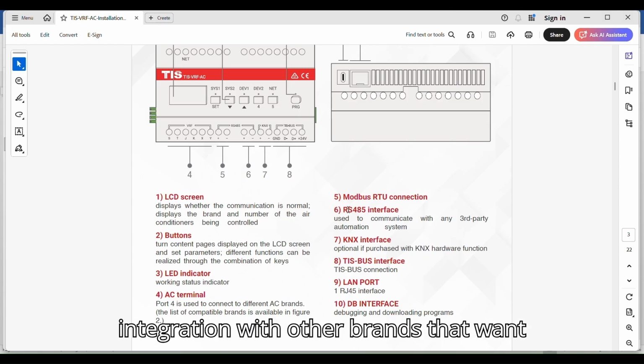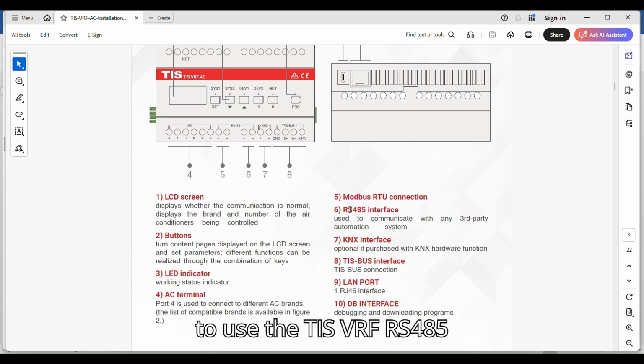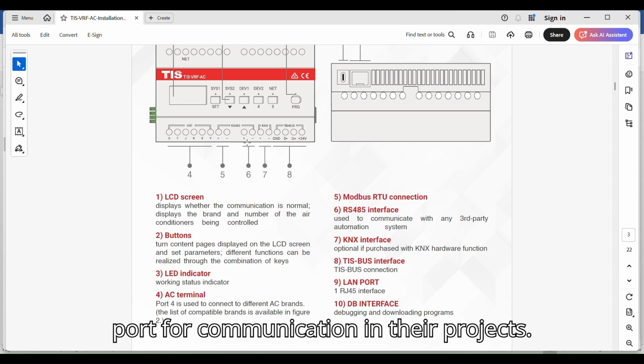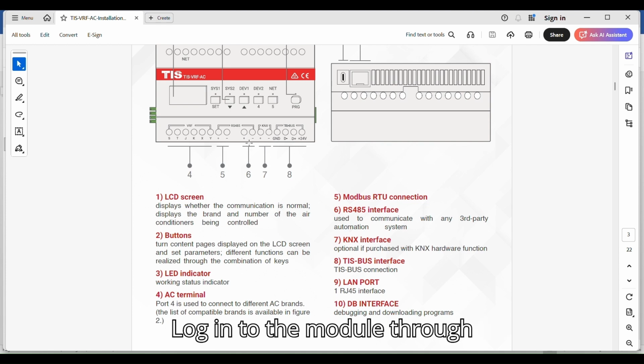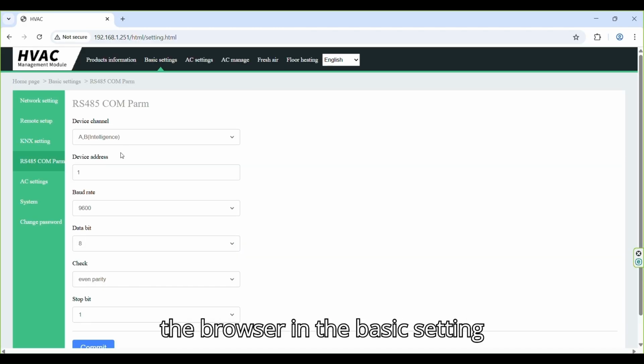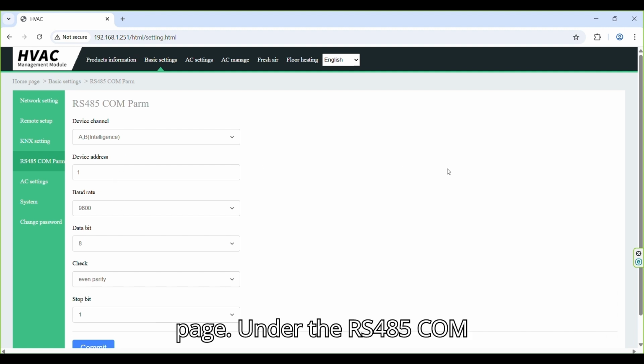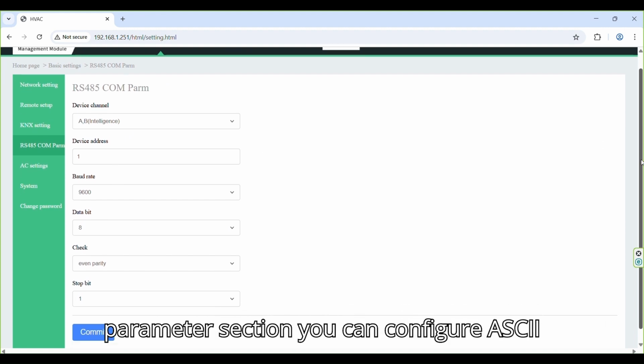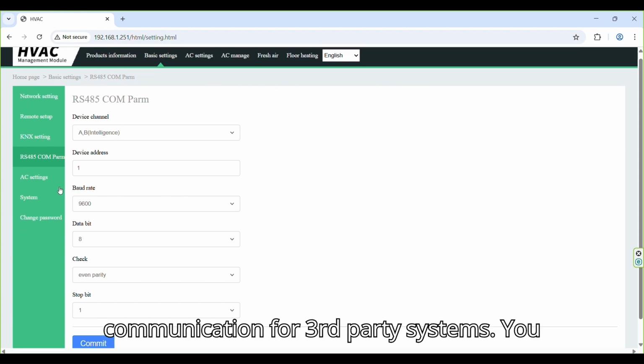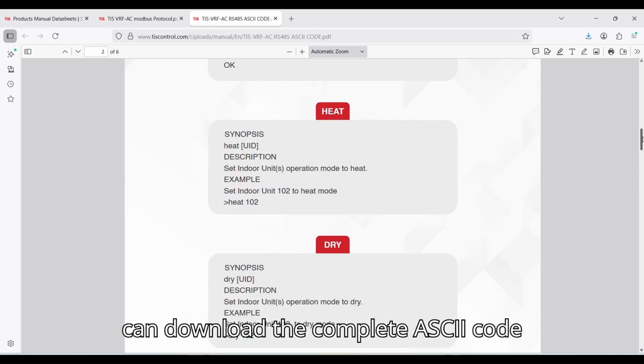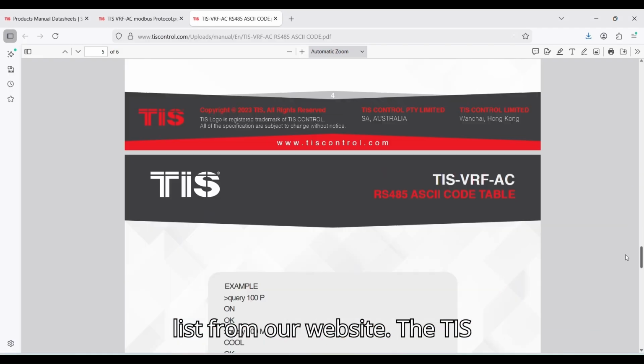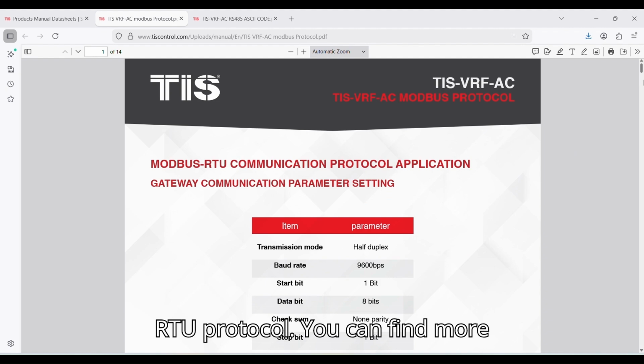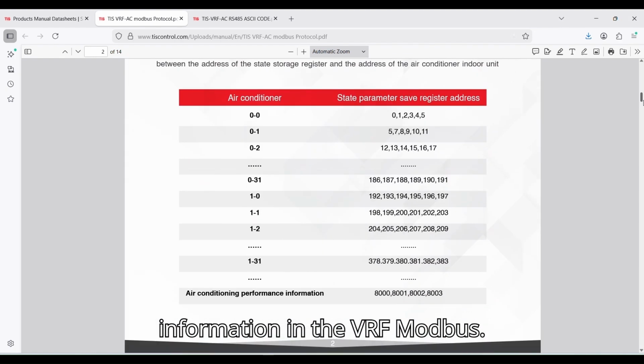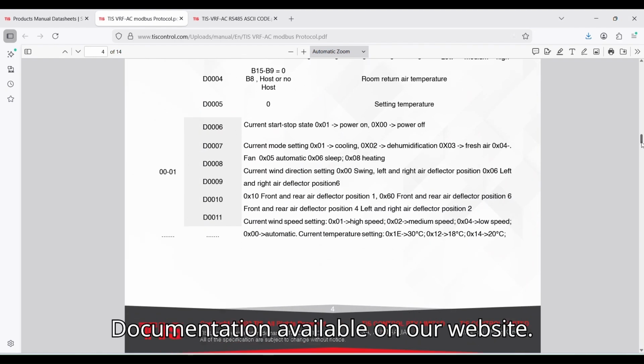For third-party integration with other brands that want to use the TIS VRF RS485 port for communication in their projects, log in to the module through the browser. In the Basic Setting page, under the RS485 COM parameter section, you can configure ASCII communication for third-party systems. You can download the complete ASCII code list from our website. The TIS VRF module also supports the Modbus RTU protocol. You can find more information in the VRF Modbus documentation available on our website.